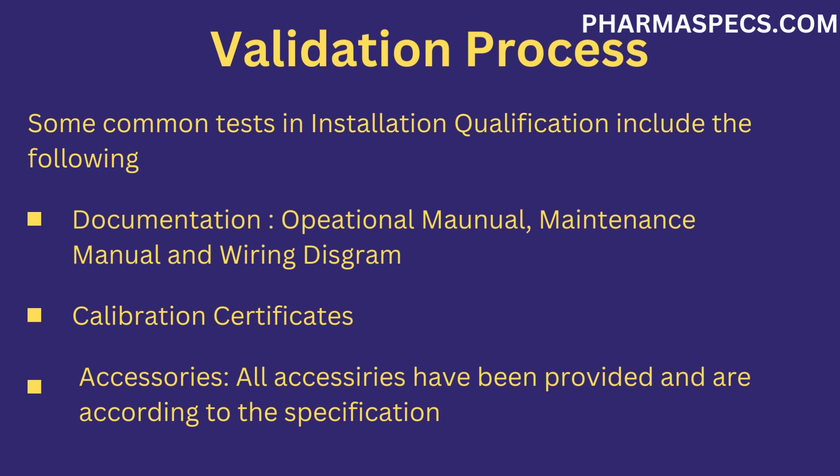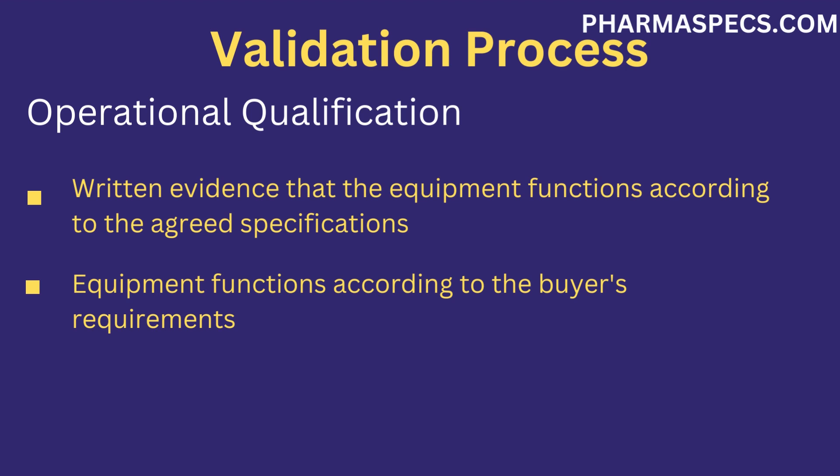Calibration certificates for all measuring devices, whether analog or digital, must be provided — examples include temperature, pressure, and air flow. Calibration certificates must be valid and not expired. The supplied equipment must also contain all the accessories that were agreed upon during the design phase.